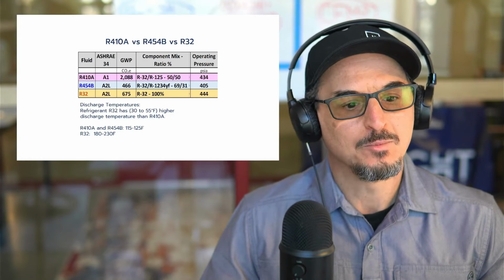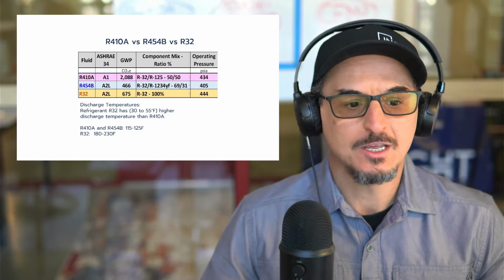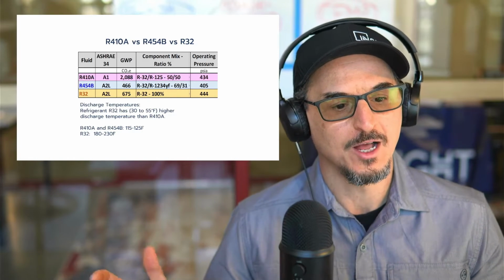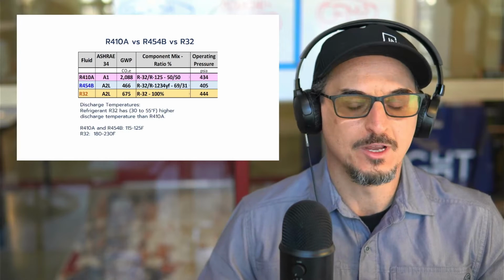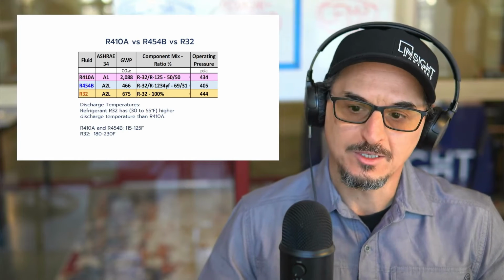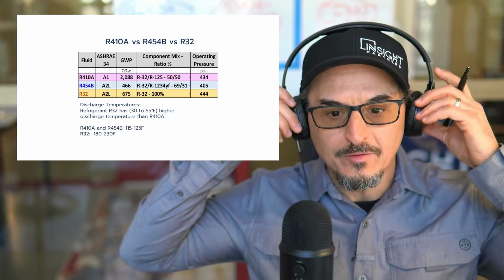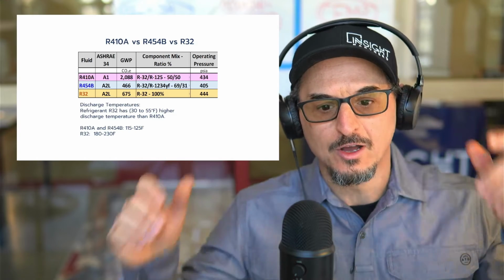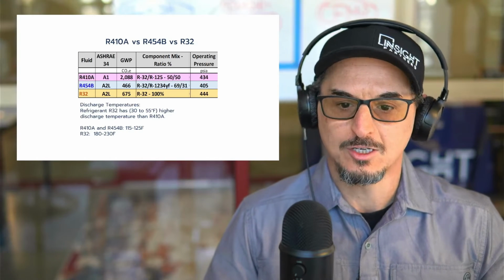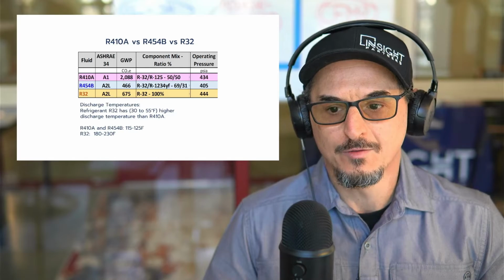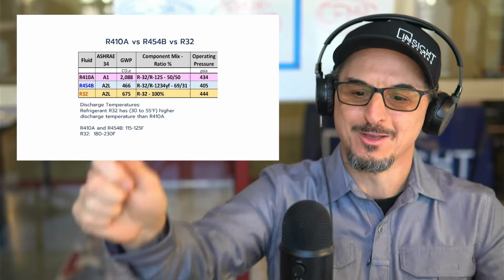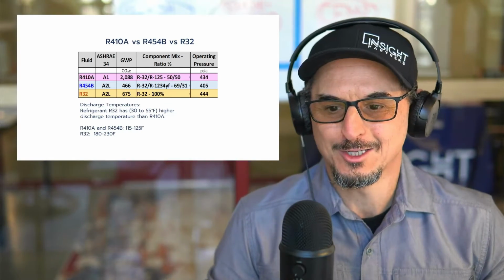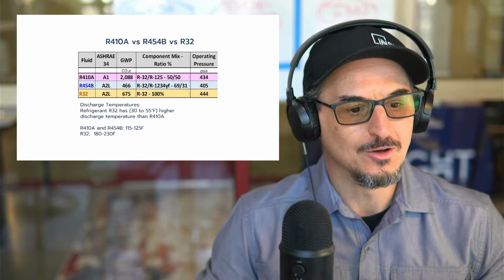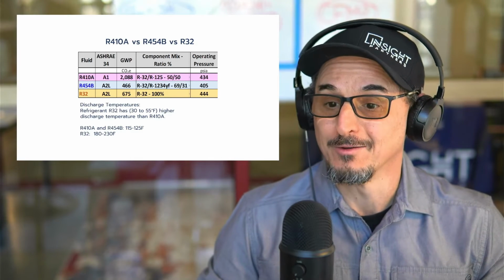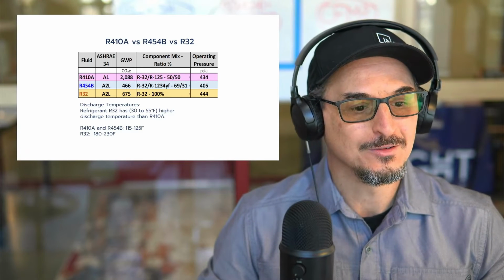The pressures are pretty similar - you can see R32 has a little bit higher pressure, 454B is a little bit lower, but in the big scheme of things, from an equipment standpoint, they're very similar. The one thing to note is R32 does have a higher discharge temperature, so be careful. If you've ever reached into a package rooftop unit and hit your forearm on a discharge pipe, it's already pretty hot - so don't do that. Don't do that with any refrigerant, but definitely don't want to do it with R32.